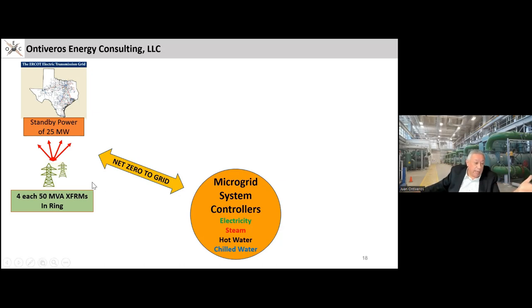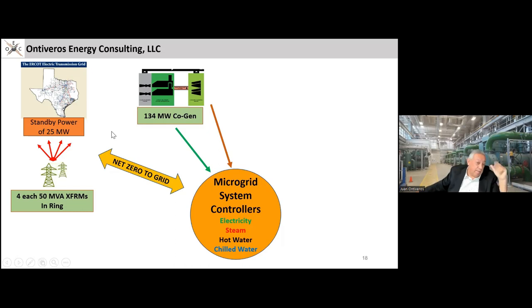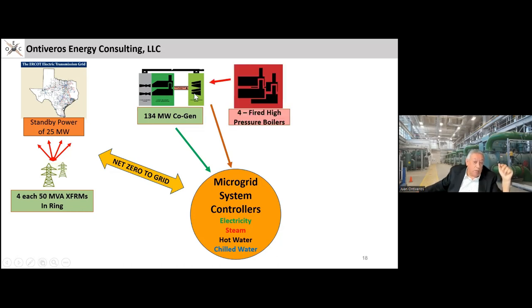That was it. So we had redundant transformers in our substation, 4 each 50 MVA transformers in a ring. So one could fail and everything still was online and you could still serve the campus. And the standby power was fed in through all four of the transformers through 25 megawatts. So then you have the generation system with combustion turbines, heat recovery steam generators, and steam turbines. So then the boilers support the steam generation and also steam to campus. So there's electricity and steam going to campus.